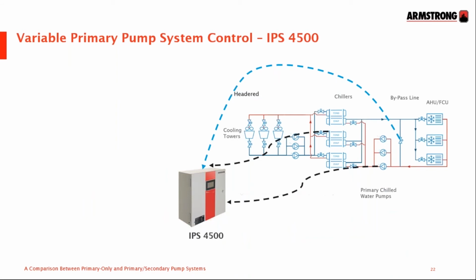So we've looked at some of the challenges involved with variable primary flow. You need to make sure that the chiller control valves operate slowly, and the speed controls speed up and slow down pumps slowly so that the chillers can catch up. Let's have a look at some control equipment that Armstrong has sold into the marketplace, and we'll look at some case studies after this. But let's look at the 4500 first, the IPS 4500.